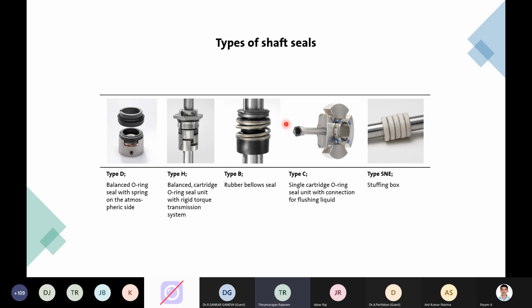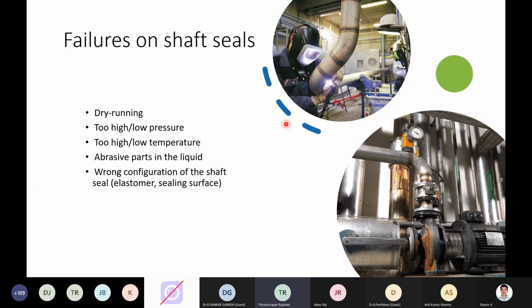Okay, these seals will not fail unless you have situations making them fail. Some situations you will find: dry running, so that will have an impact on your pump operation, because once your suction is completely choked or clogged, or the foot valve has failed, a dry running situation happens. High or low pressure or high temperature, because these seals are temperature sensitive and pressure sensitive; the seal is designed for 16 bar, and if it is mistakenly operated at excess pressure, the seal will fail. And abrasive particles in the liquid, because all these pipings are welded before completion, so there is always a chance that a lot of impurities, like metal particles, are present. So we insist on thoroughly flushing the lines before the pump is installed, so that those impurities will not settle in the mechanical seal of the operating pumps. And the last one is wrong configuration of the shaft seal. Maybe your seal or sealing surface, if improperly designed, then you have a chance of seal failure.